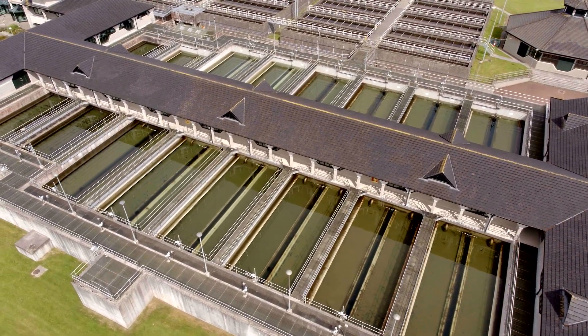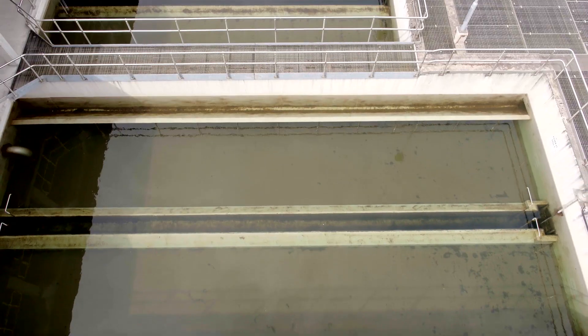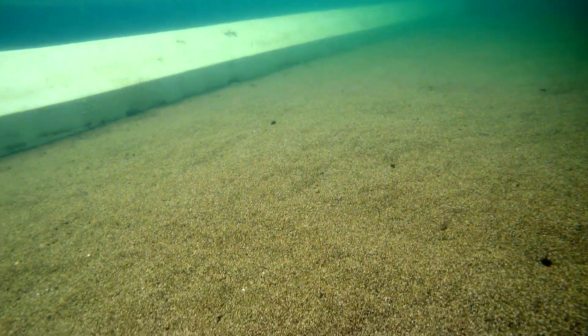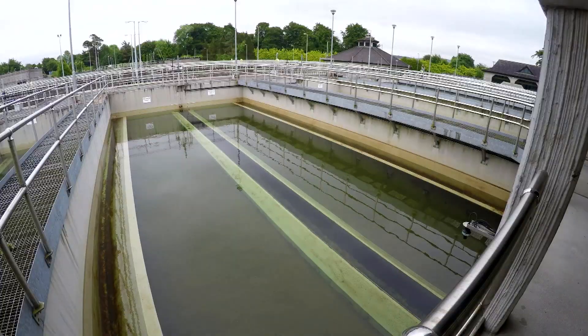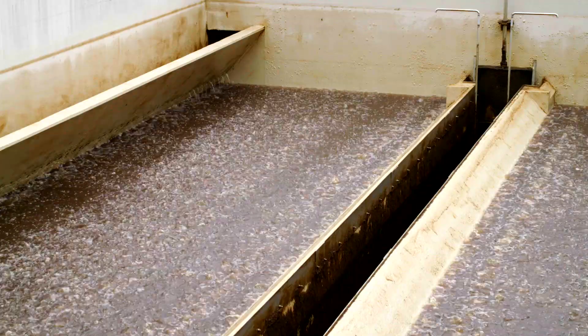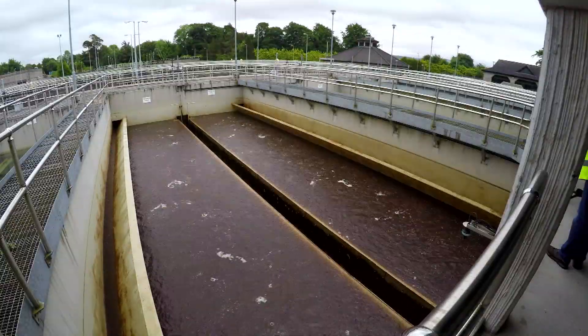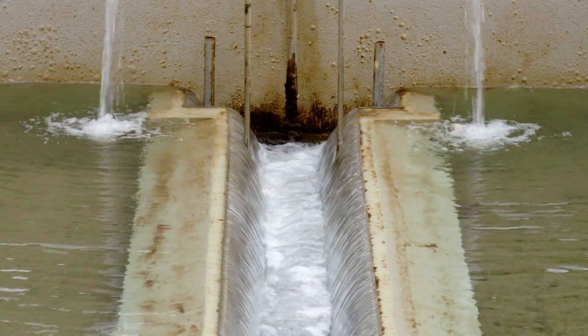And this is where it comes next. These are the filtration tanks. The bottom of each tank is covered with sand. The water passes through this sand, and any fine particles and microorganisms get trapped in the tiny spaces between the grains of sand, allowing only the water to pass through. The sand is used over and over again for up to 10 years, so it has to be cleaned regularly. This is done by blowing water and air through the sand to dislodge the dirt. The clean sand can then be used to filter more water.